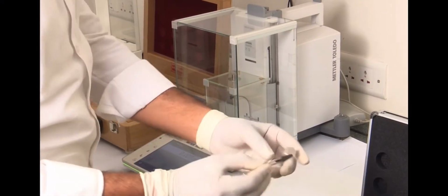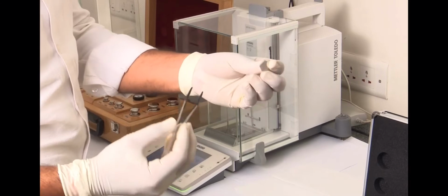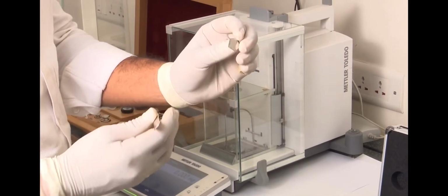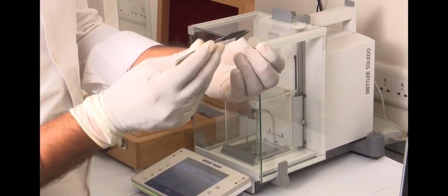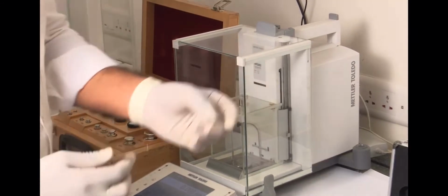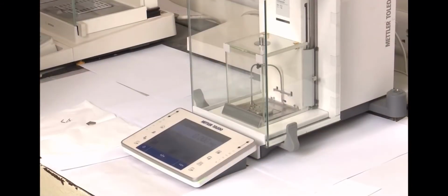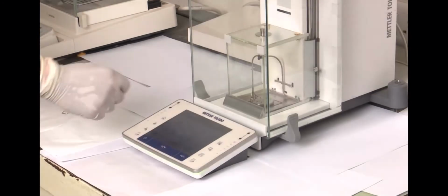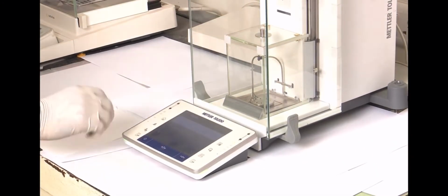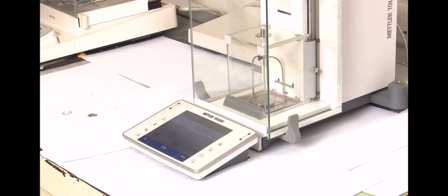This is the weight under calibration having denomination 500 milligrams. Its material of construction is steel and it is pentagon in shape. Before calibration, check that the balance is leveled and cleaned. Press tare button on mass comparator to make the reading 0.